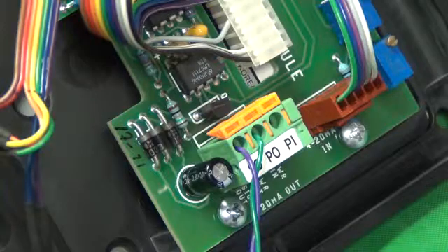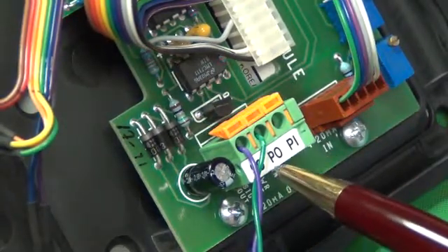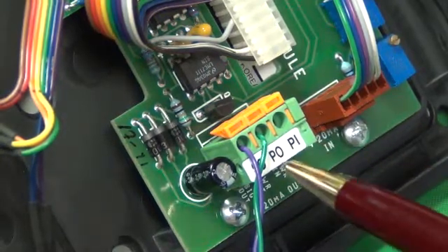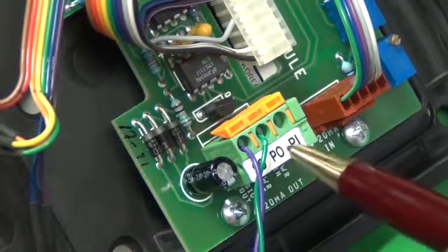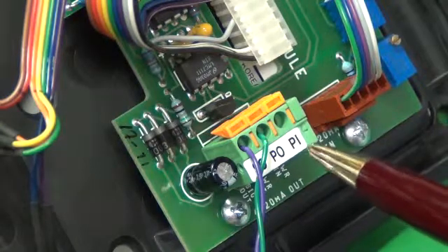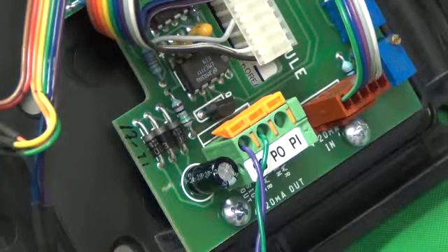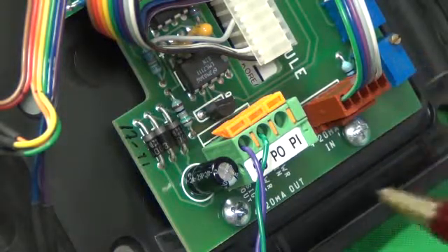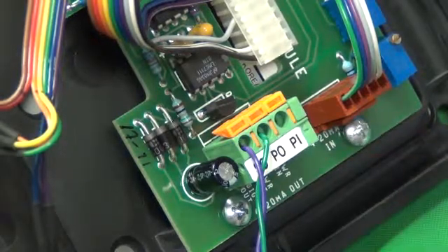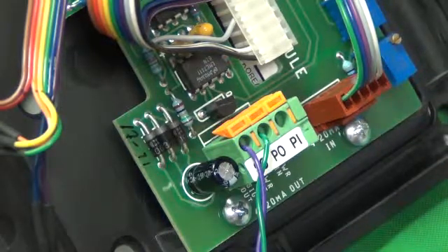So we'll simply look at our 3 terminal block points, which are SO, PO, and PI. SO is the signal into which the violet wire is placed, secured. The next is PO and PI. We've chosen in this case to use PO because the controller is powering the 4 to 20 milliamp signal. If that were not the case, the PI would be used if you had an independent supply for the 4 to 20 milliamp signal.